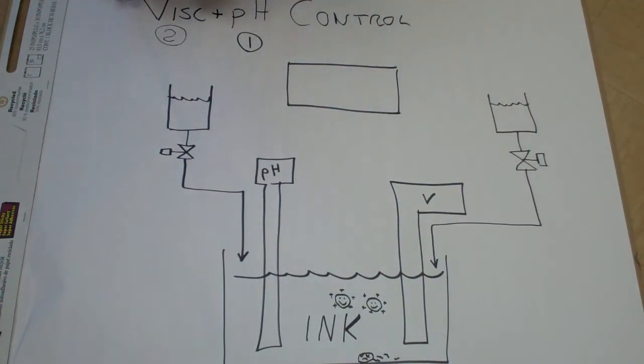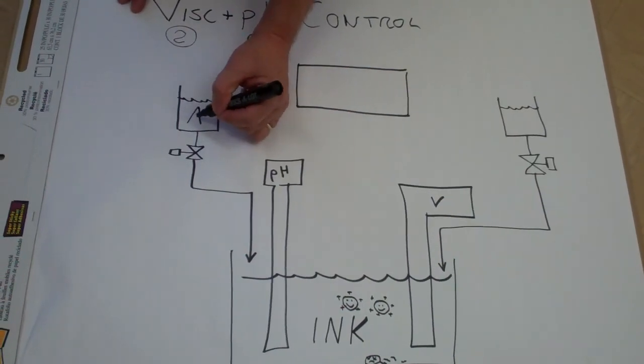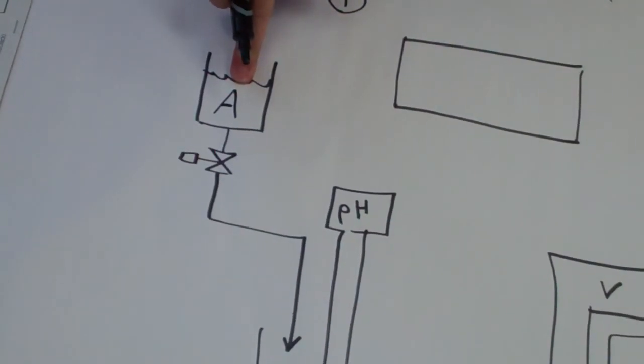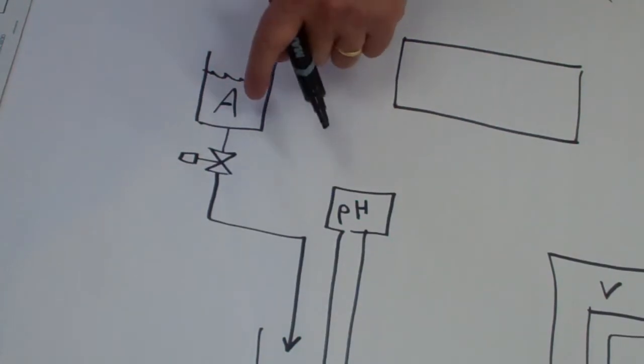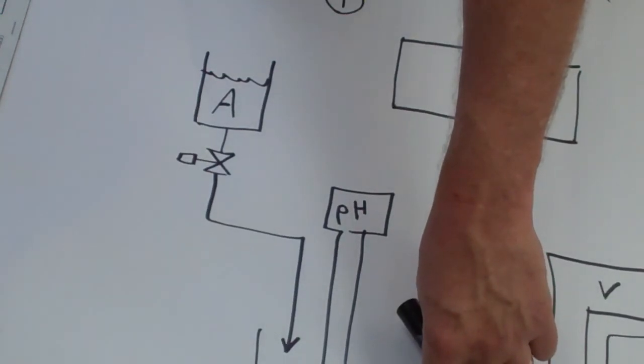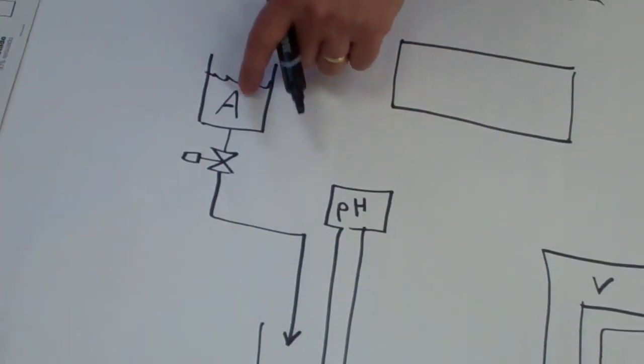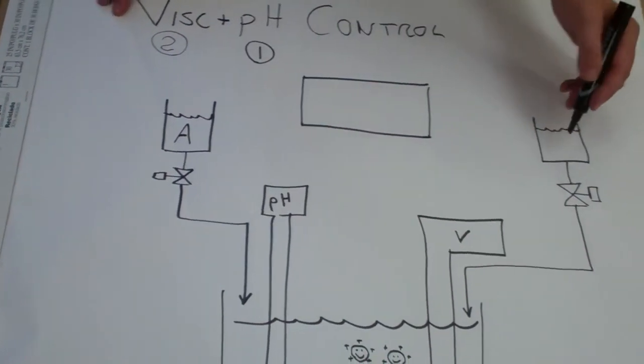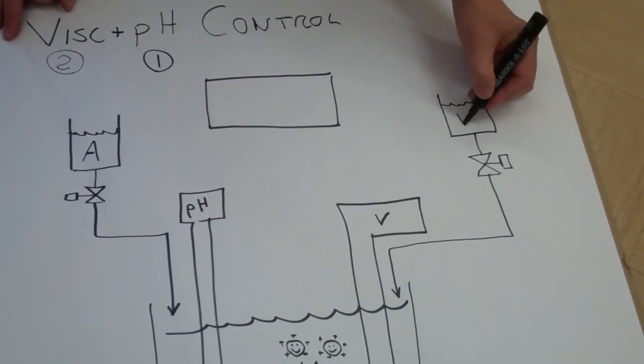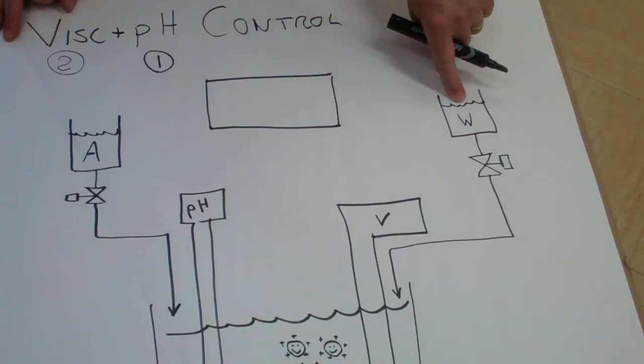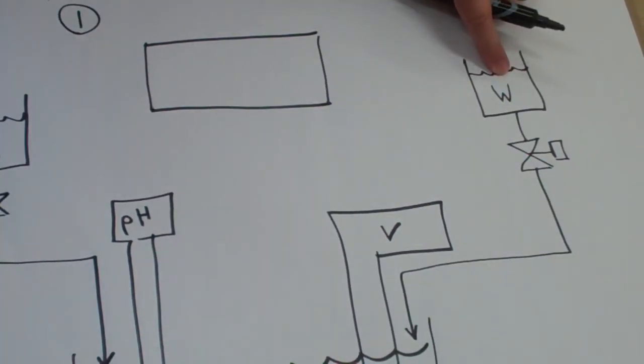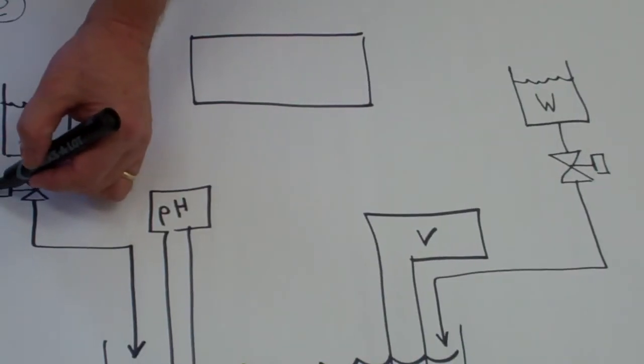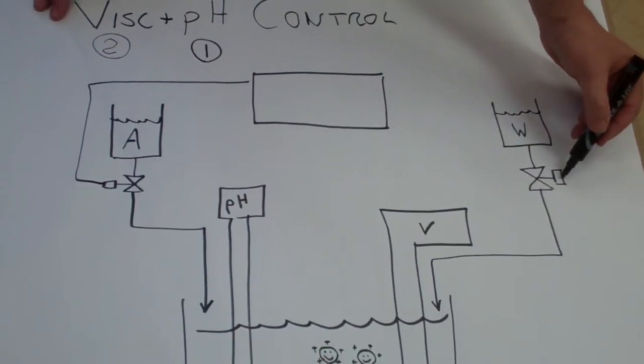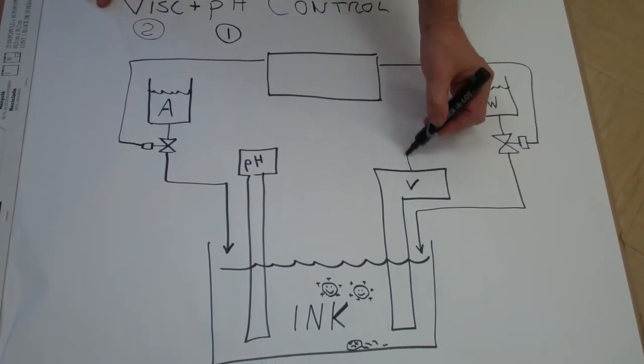You can further have a container with an ammonia solution, often called amine, which should be appropriate for the ink you're making. So talk to the supplier of your ink to ask them what you should be diluting at. Over here, you'd have a water supply, which is used for viscosity control. These are two-way valves. They wire back to the controller. These wire to the controller.